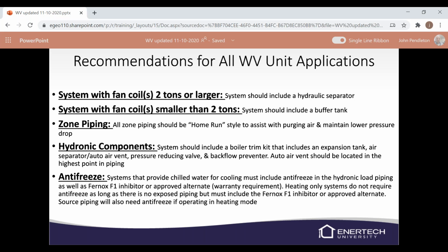Make sure we're installing a boiler trim kit that's going to include an expansion tank, air separator and air vents, pressure reducing valves if you've got some makeup water, and backflow preventers. Make sure you're installing the auto air vents at the highest point in the piping of your system.